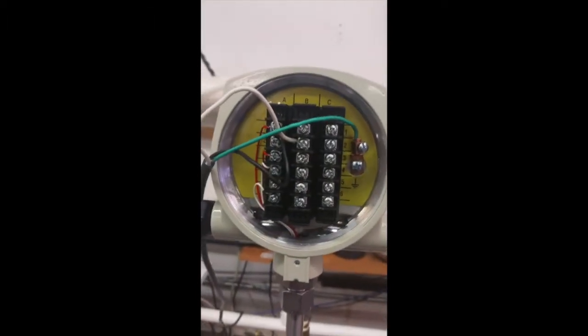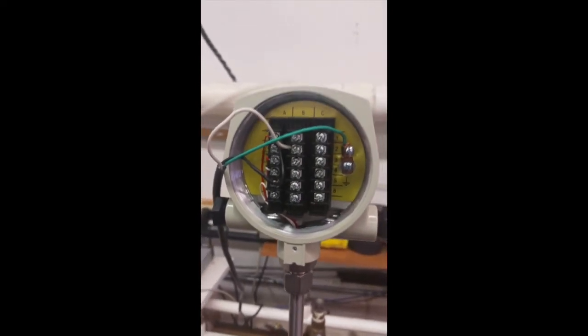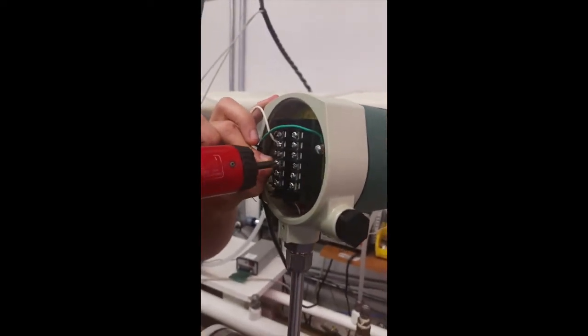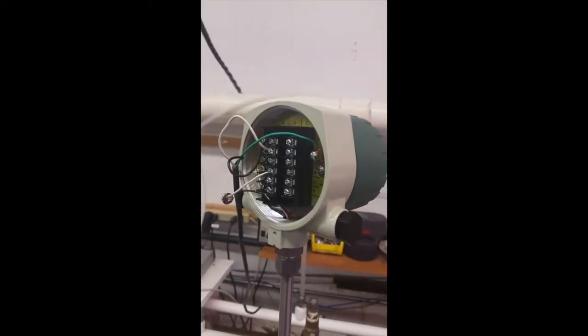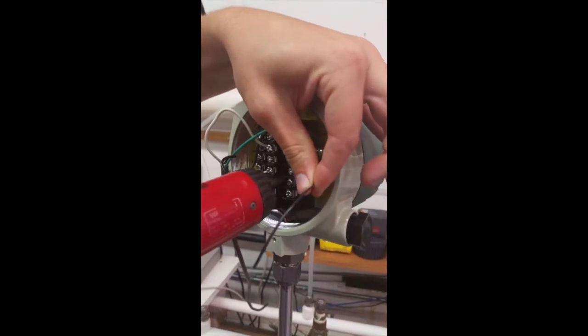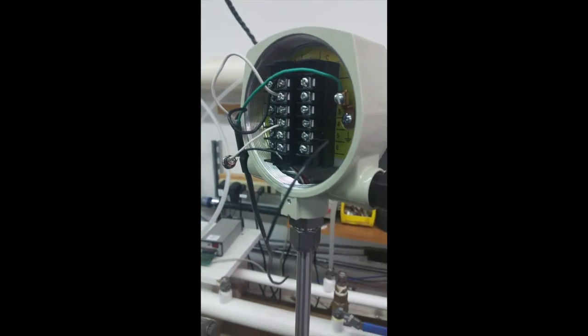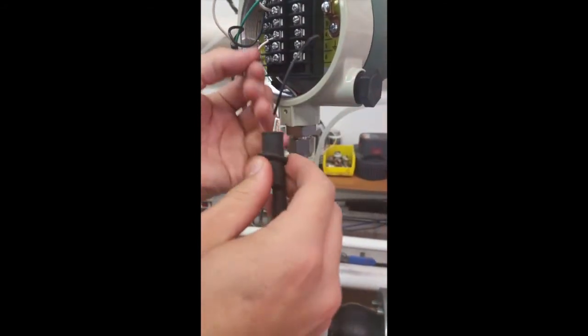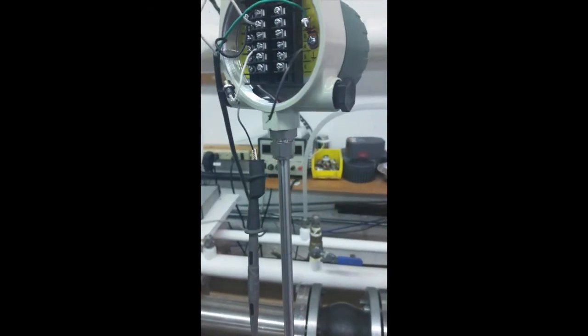Now it's time to connect the 4 to 20 milliamp with external power. So to create the loop, first Kyle's going to connect the positive wire to B4. Next he's going to connect the return wire to B5. This will create the loop for the externally powered 4 to 20. And this is what a proper wiring looks like for that 4 to 20 milliamp externally powered output.